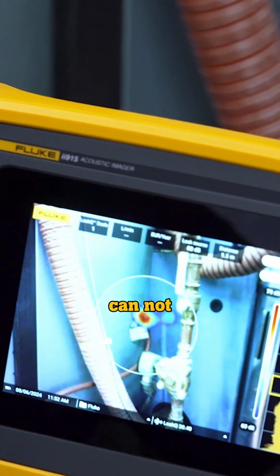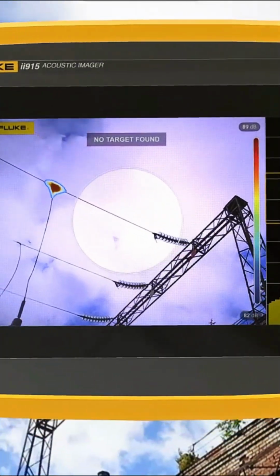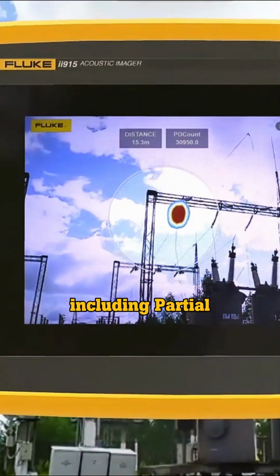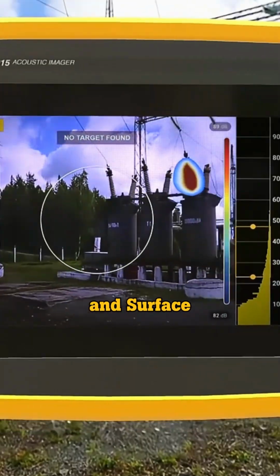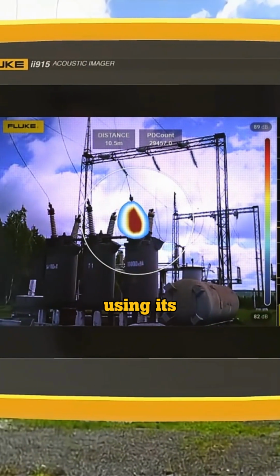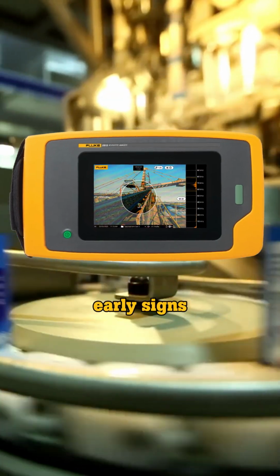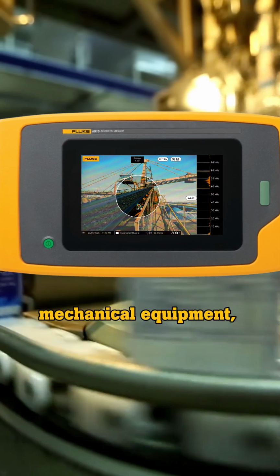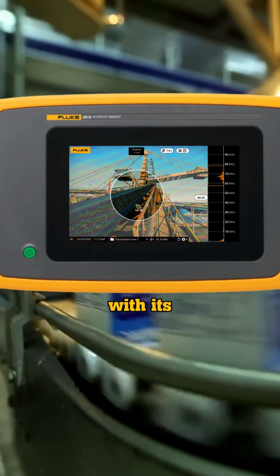This means it can not only detect hidden leaks, but also other invisible issues, including partial discharge, corona discharge, and surface tracking on high voltage equipment using its PDQ mode, as well as the early signs of problems in rotating mechanical equipment, like conveyor bearings, with its MechQ mode.